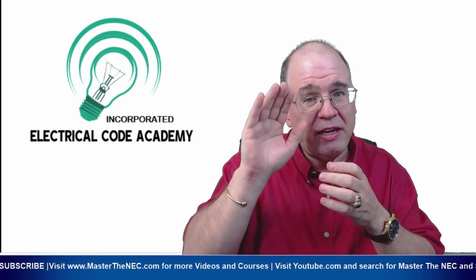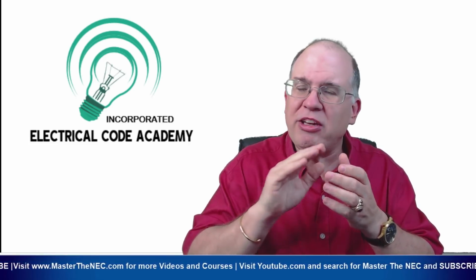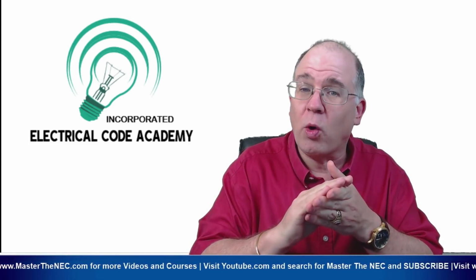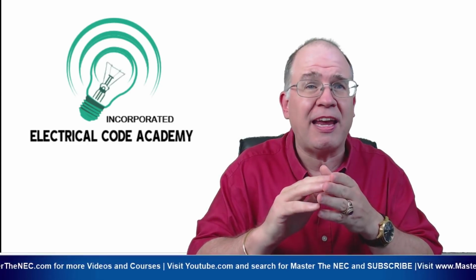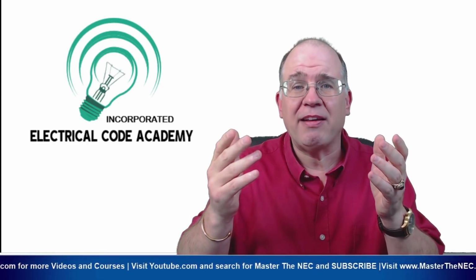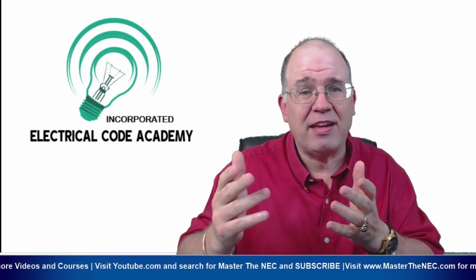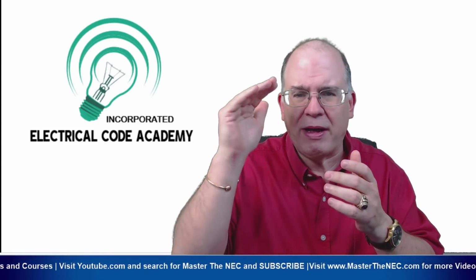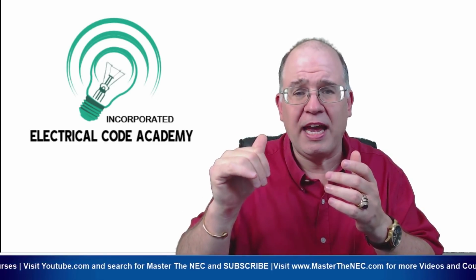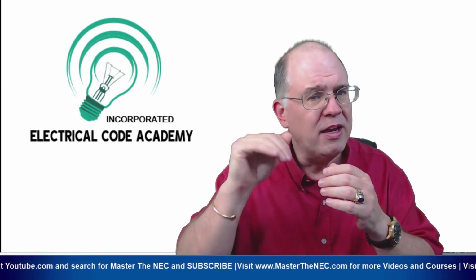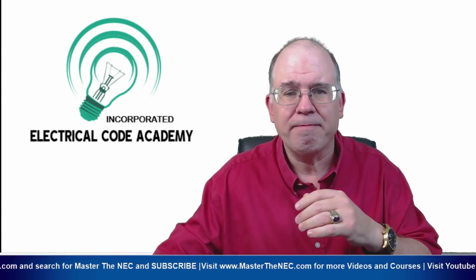So this rule here means you have to meet all of the rules, and we do give you an exception for when you have more than 20 current carrying conductors, but the only exception is saying, okay, you've got to do an ampacity adjustment at 60%. You don't have to worry about all those tables in 310.15(B)(3)(a). Just go right to 60% and apply it, and there you go, okay?